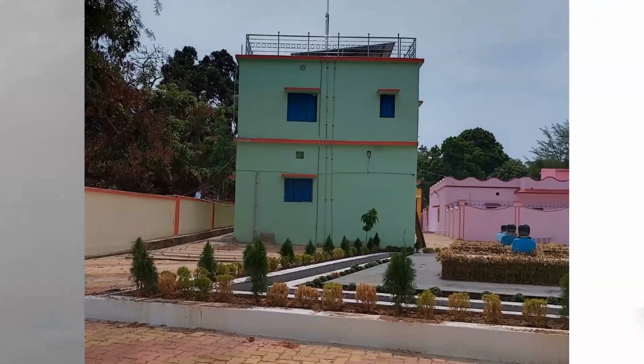In practice, what will happen is if there is a lightning strike on this building, the down conductor carries an enormous amount of current, and the vertical pipe and the electrical installation going from top to bottom of the building, there are two down conductors and one electrical wiring, this electrical wire and the connected equipment will disappear immediately. Disappear in the sense it is completely going to burn. It will burn the rooftop solar PV system. Also, it is going to burn all the electrical items connected on the other side of this particular line. So basically, you have to have a number of down conductors, depending upon the size of the building, throughout the building. The idea is that lightning current is separated into several paths, or diverted through several paths.